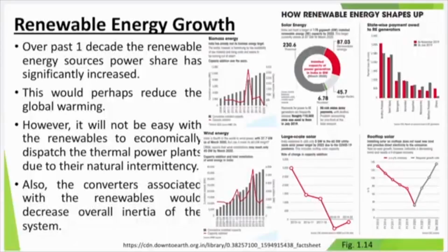This is because those huge generators do carry inertia within them. That means they do store some energy within themselves. As and when there is an oscillation of requirement, they provide that inertial power. Okay? And hence we don't realize any mismatch between my requirement and its availability.